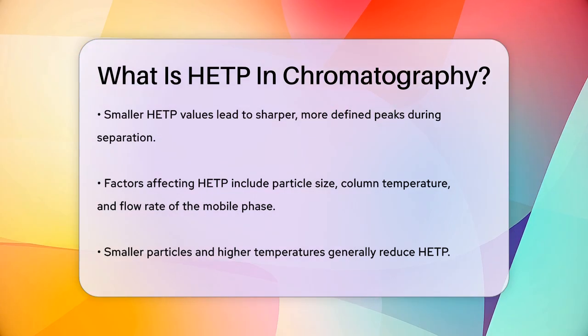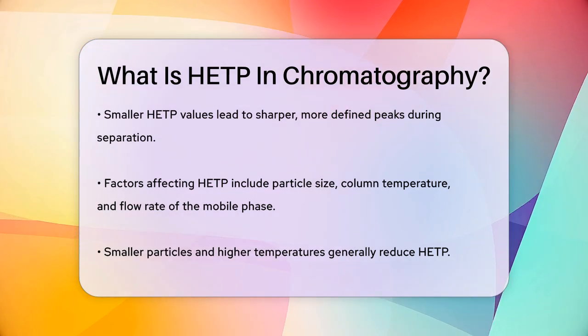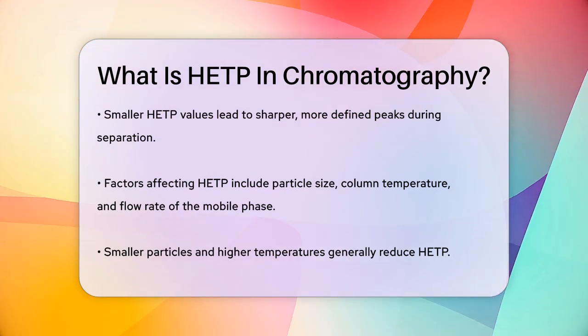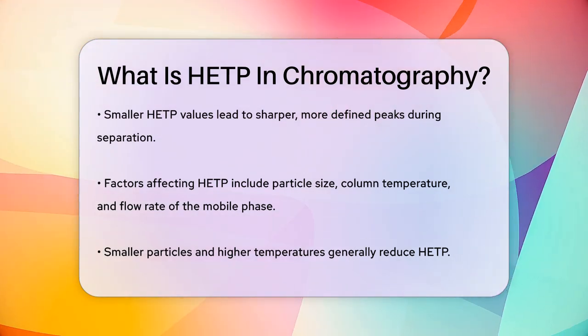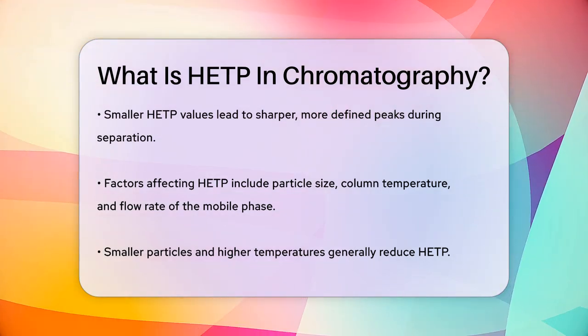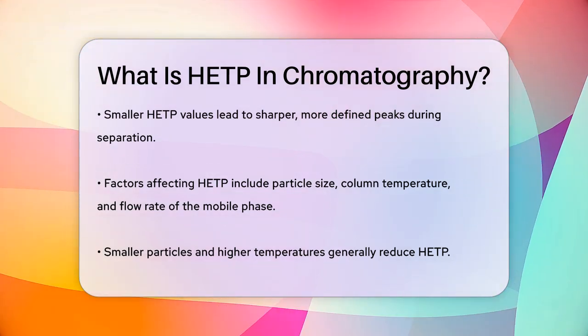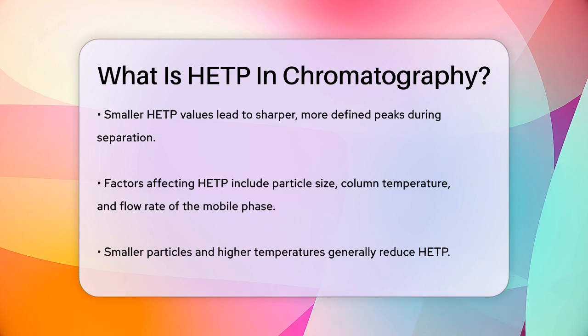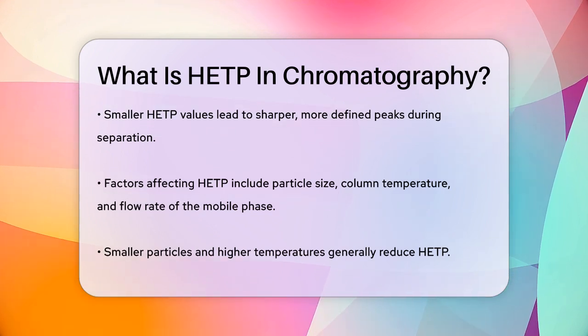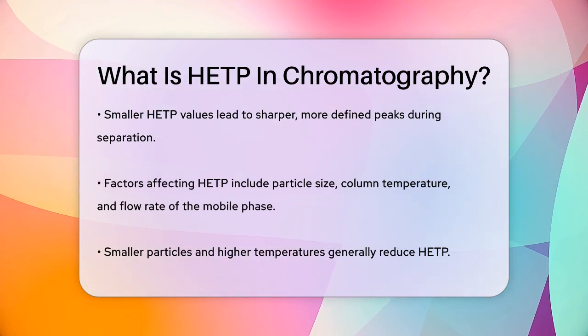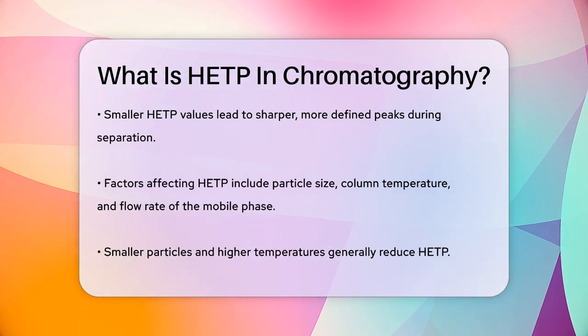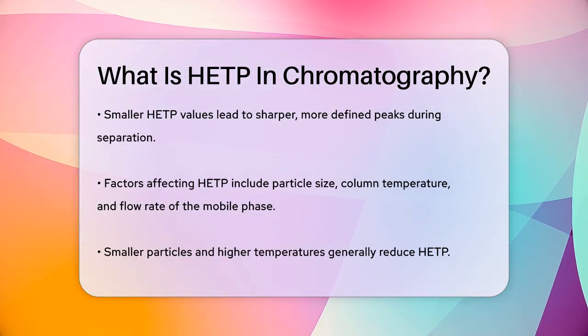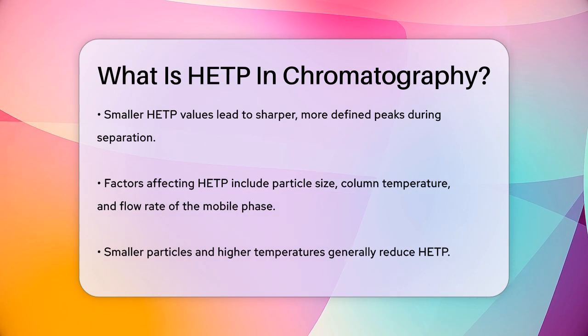There are several factors that affect HETP, such as the particle size of the column material, the column temperature, and the flow rate of the mobile phase. For example, smaller particles and higher temperatures can reduce HETP, while higher flow rates can increase it.